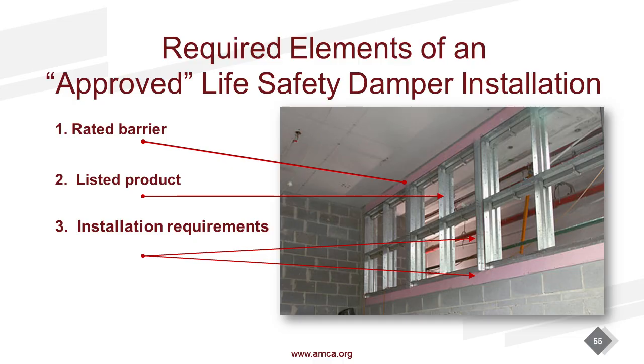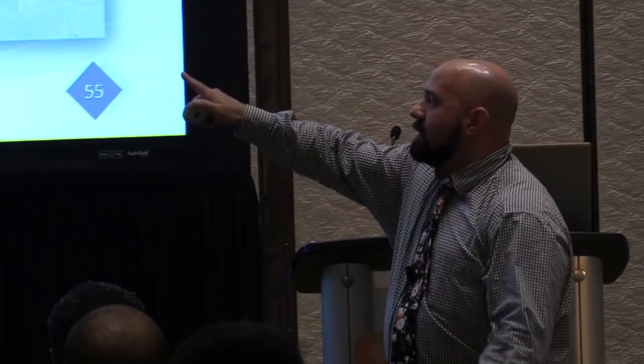Or my building inspector, my contractor says, hey, I got to run my ductwork at an angle. I need to install the damper this way. We'll read the instructions. Dampers must be plumbed square and straight. So make sure the barriers are good, then you're good. You have to select the right listed product. We all know how to do that. We know what the rating of our barrier is. We know what the test standards are. We know where to find it in the code. We select the right product.